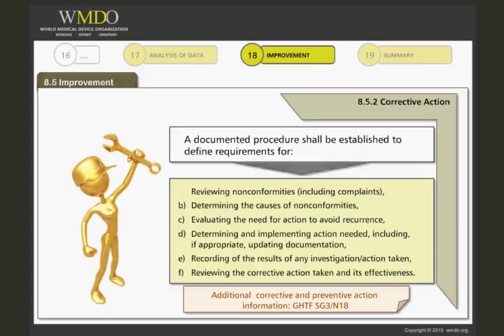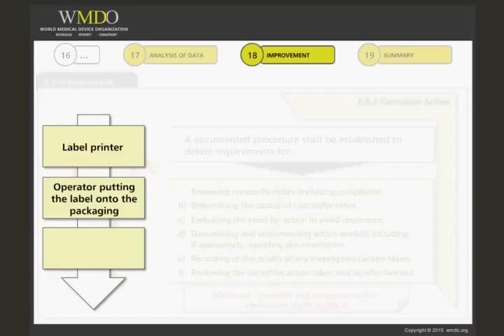Let us discuss a short case study to illustrate the different steps and the meaning of the wording used by the standard. Imagine you have a labelling line made of a conveyor belt with the following workstations: a label printer printing the label for your finished medical device's outer box; an operator putting the label onto the packaging box; and a quality control operator that controls the labelling — checking if the batch number is correct, if the label is correct, matching the product type, etc.